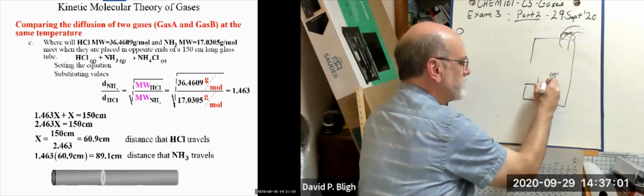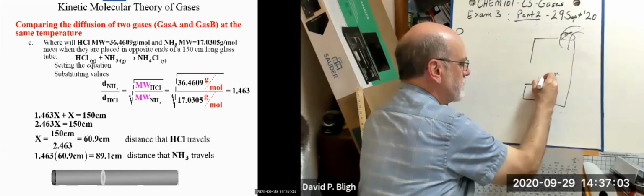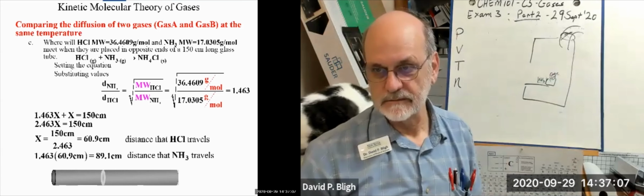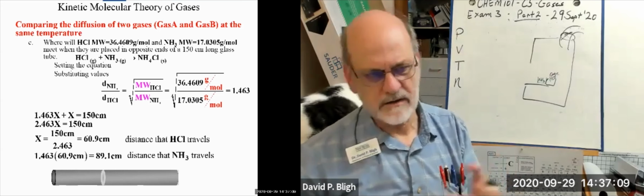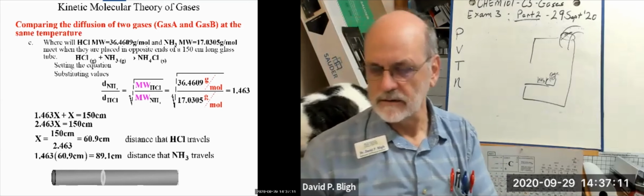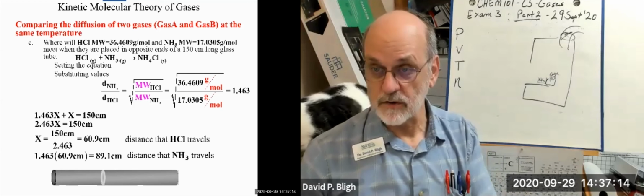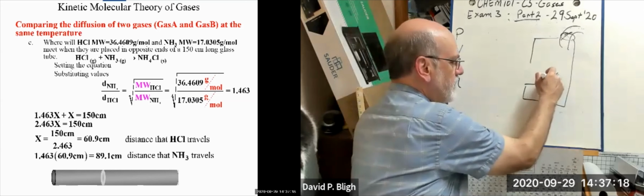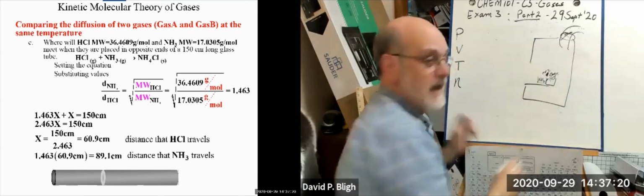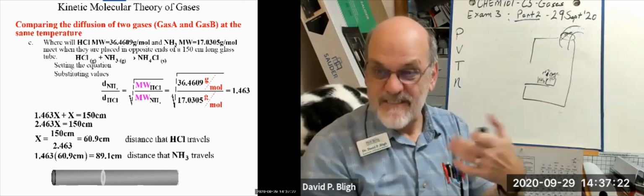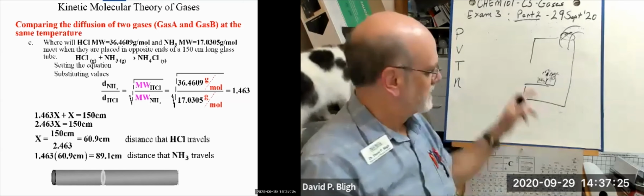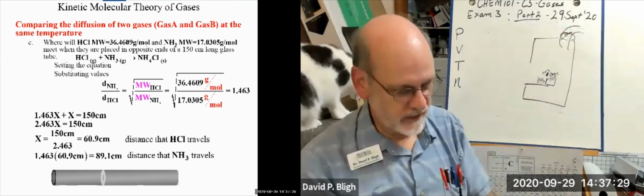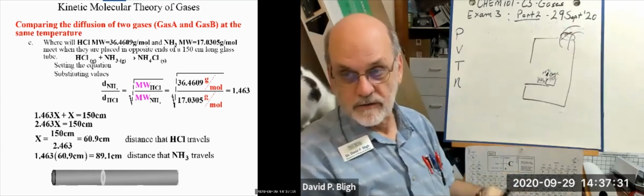And right next to it, we put a container of liquid ammonia, like it's not pure ammonia, but just ammonium hydroxide solution, and it also vaporizes ammonia. They meet here, and they form a visible fog, which is swept into the unit, and you can see that it's moving. See, the air is moving in your fume hood.